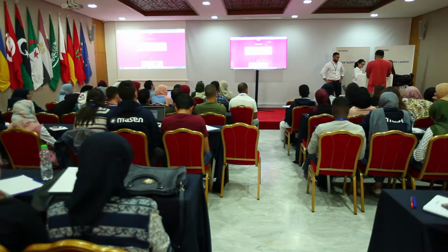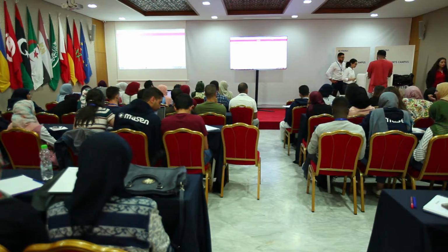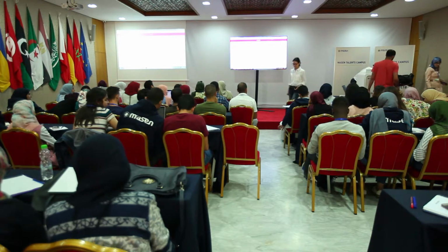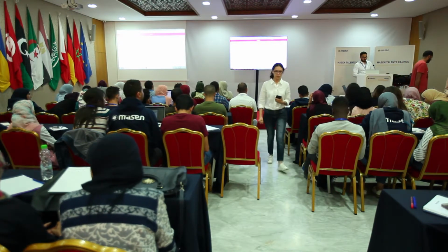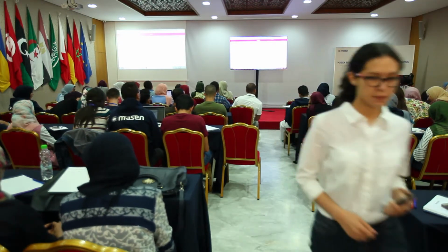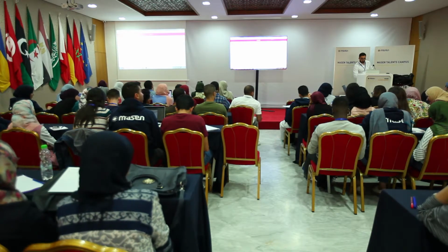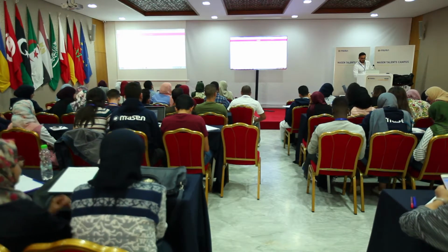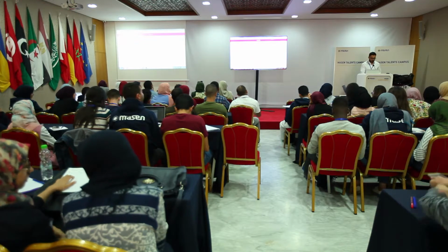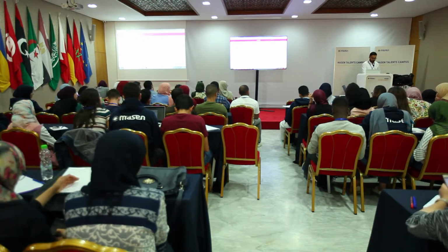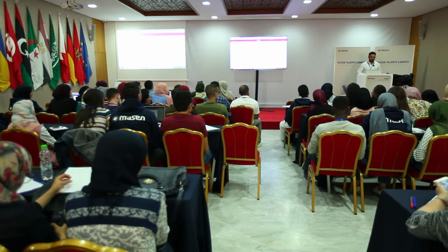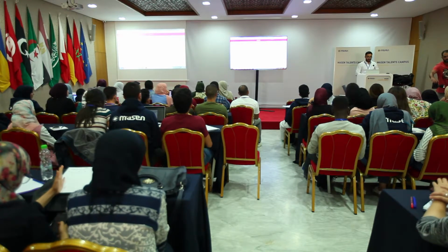So that's why we play with the size of the field and how I want to operate. Of course, if I increase my solar multiple, if I collect more than that, basically I will be able to operate more often at 100% load. And then what will happen is also that this extra energy I could store. So that's one of the reasons why you will increase the solar multiple.